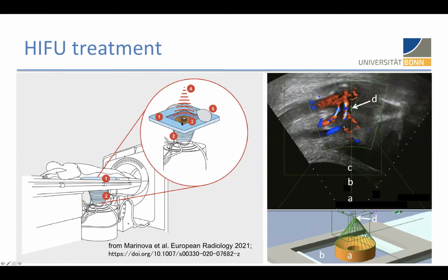The therapeutic ultrasound beam was transmitted by a 20 centimeter diameter ceramic transducer with a focal length of 15 centimeters, operated at a frequency of 0.8 megahertz. To compress the stomach and dislocate the bowel away from the acoustic path, a balloon filled with degassed water is positioned between the transducer and the skin of the anterior abdominal wall. During the HIFU procedure, the extracorporeal therapeutic transducer generates an ultrasound beam forming an oval-shaped focus sized 1 to 3 millimeters in width and 8 to 15 millimeters in length.